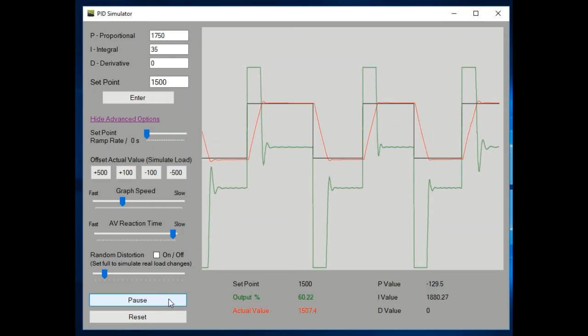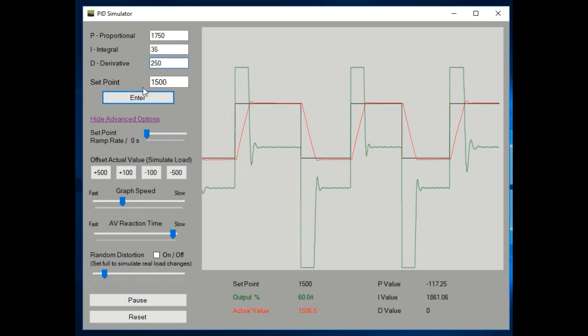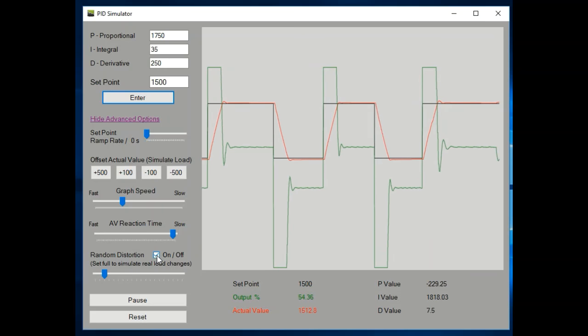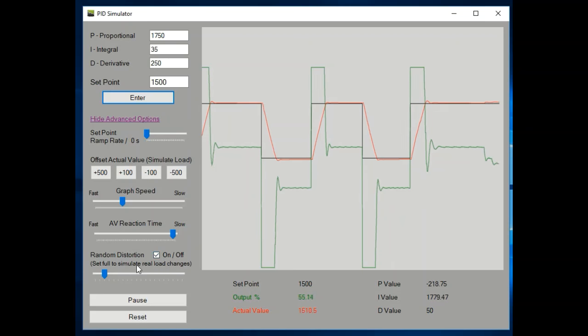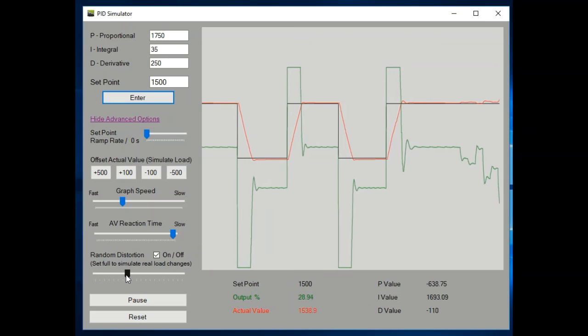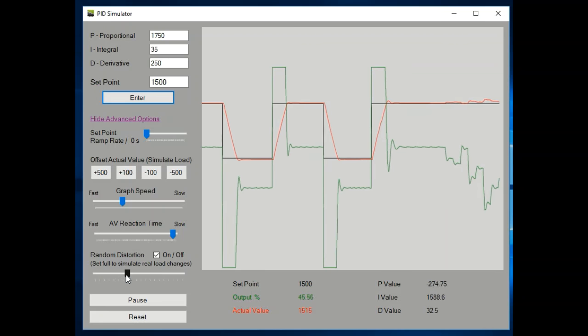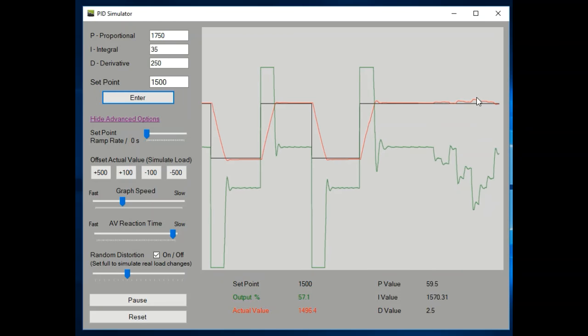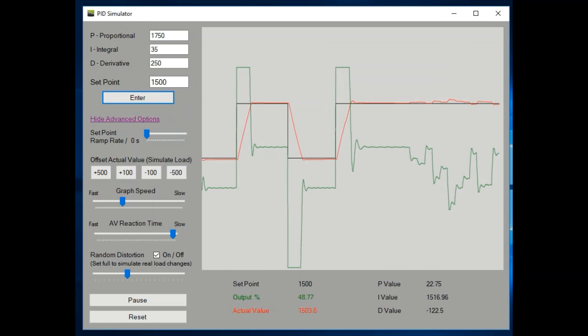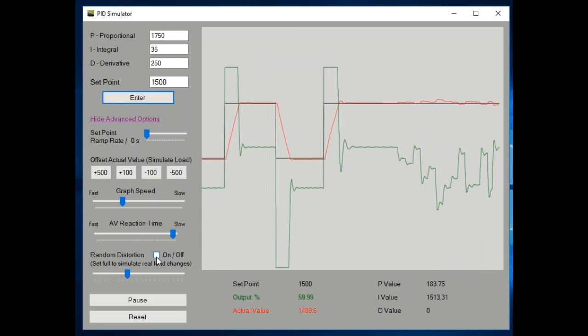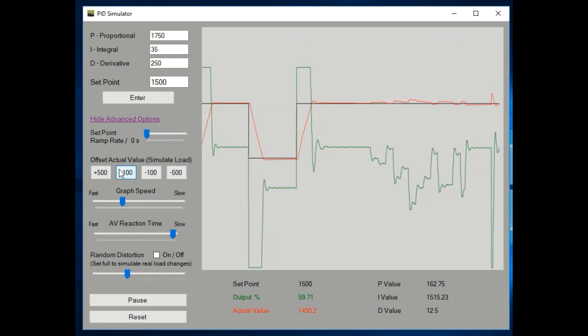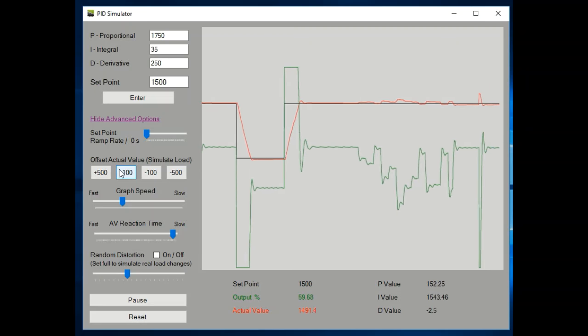Now with this controller, once you have all of that in play with our P, I and D set, we can start playing and tuning different scenarios. If we decide to add a bit of distortion into the loop — distortion can also simulate load changes, so the more you increase the distortion the larger the load changes. The output seems a little bit up and down, but notice how with the changes in the actual value it's actually bringing it back to the set point — it's doing what it's supposed to. Take the distortion away and the controller should smooth out. Add a load step and see what the reaction is — a very good, fast acting and smooth controller.